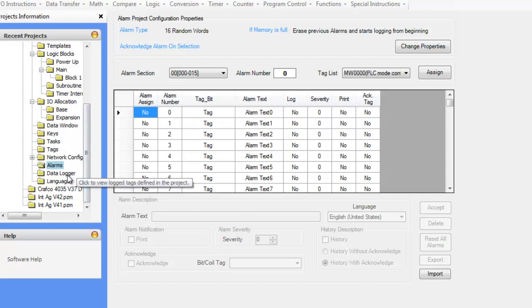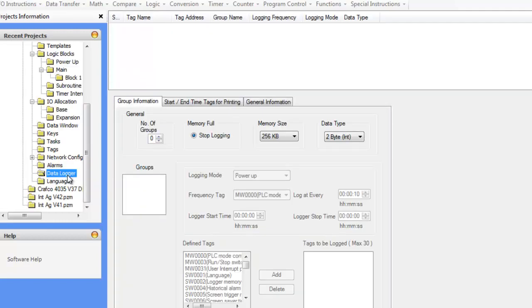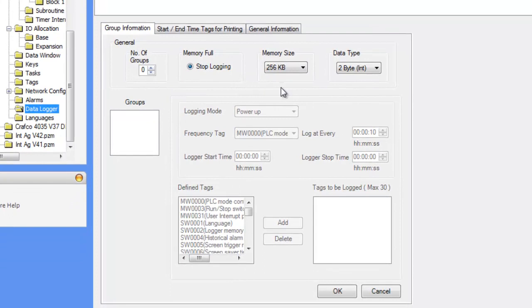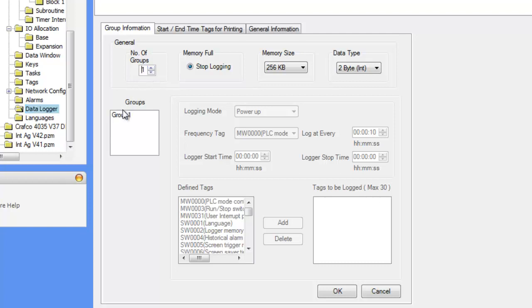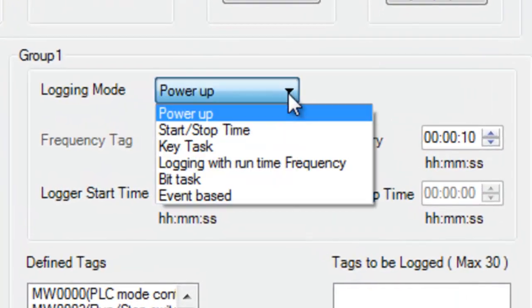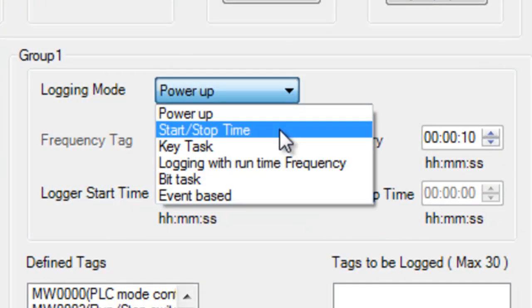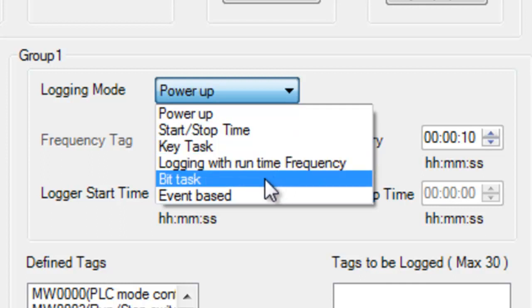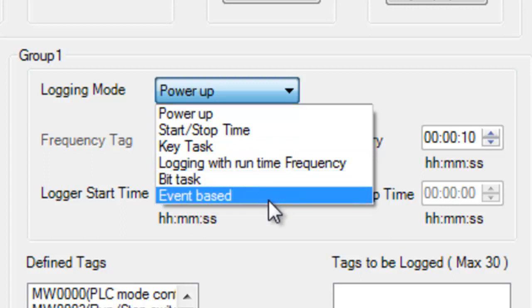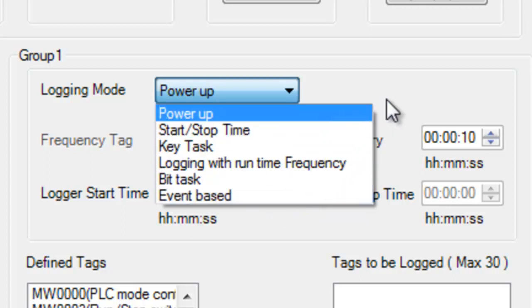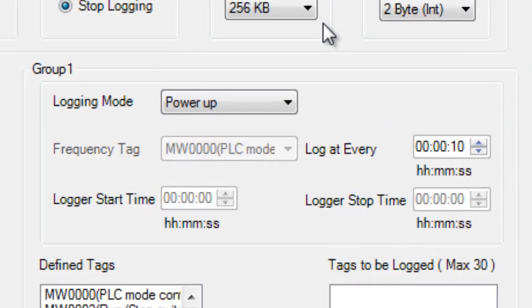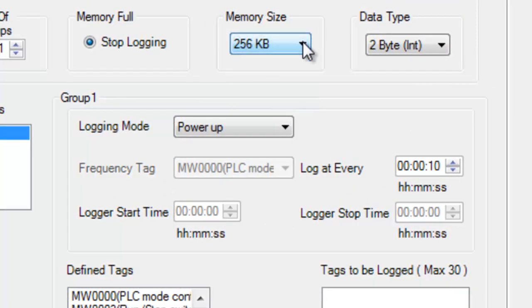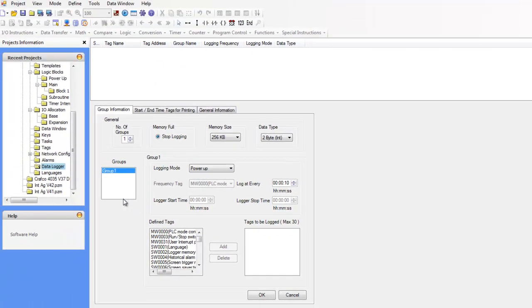We also have a powerful data logger. And this data logger allows us to define up to four groups of logging families. So if we choose one here, you'll see we have group one. Now we can choose the logging mode. So we can do power up, start stop time, key task, logging with runtime frequency, a bit task, and an event based logging. This is very powerful that you can define exactly when you want this group of tags to be logged.